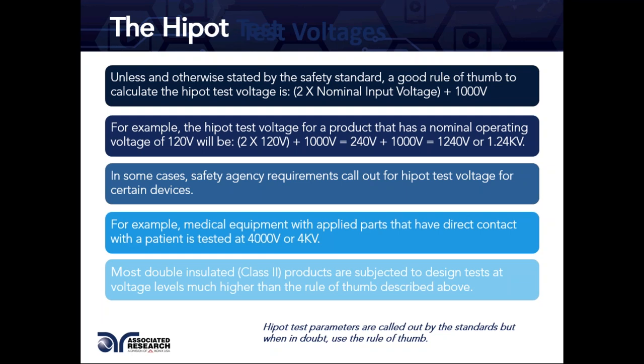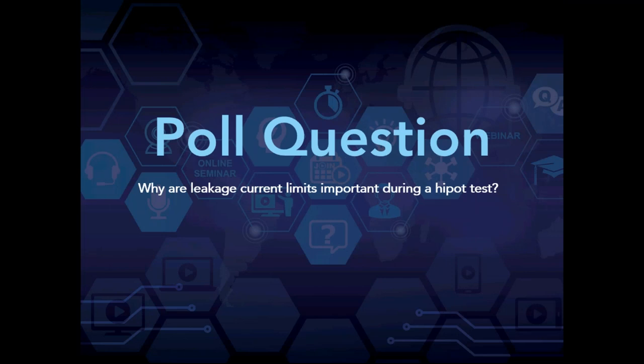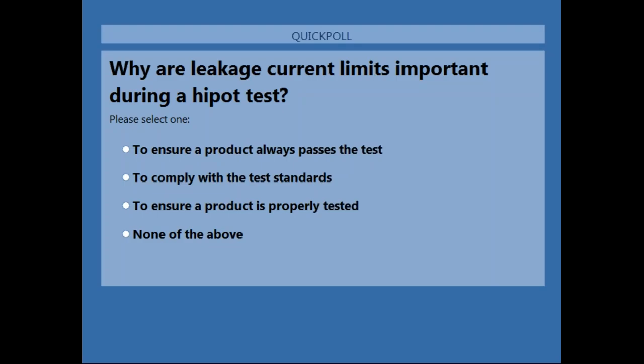The important takeaway is that Hipot test parameters are called out by test standards. When in doubt, use the rule of thumb: twice the voltage rating plus 1,000 volts. That leads us to our first poll question: why are leakage current limits important during the Hipot test? Please take a moment to participate.